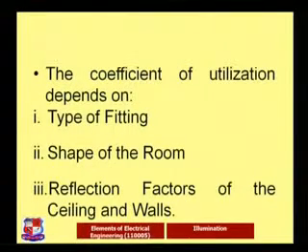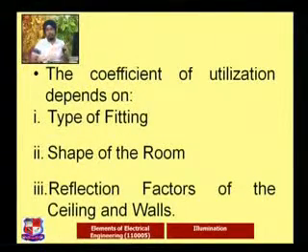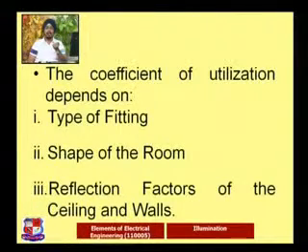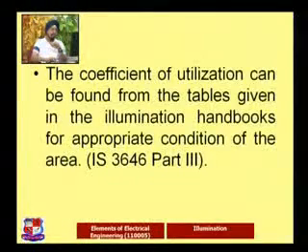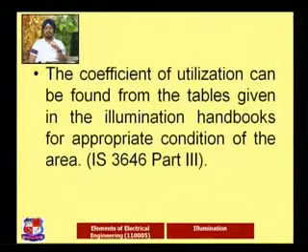So that's why this coefficient of utilization depends on the type of fitting we are going to use, the shape of the room, even the area, and the reflection factor of the ceiling and the walls, meaning how much of the energy they have absorbed and how much they send back onto the object. The coefficient of utilization can be found from the table.